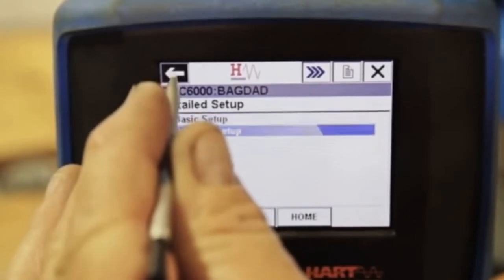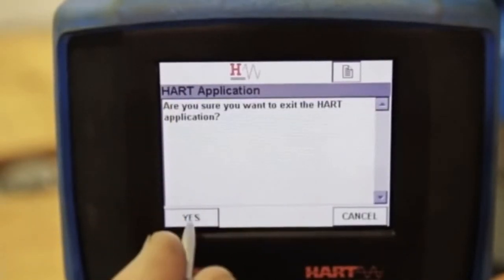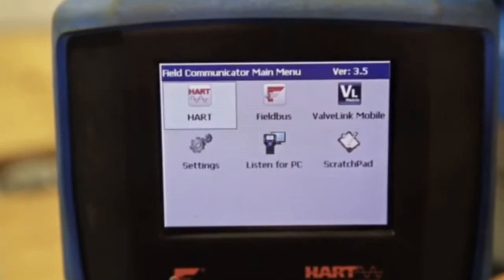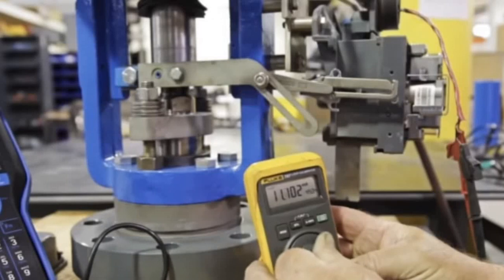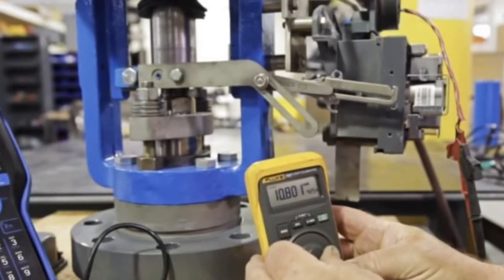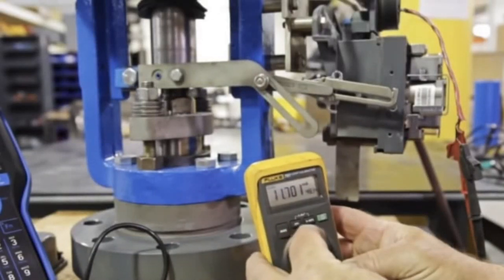Arrow back to exit out of all the screens. Select Yes to exit the HART application. Calibration is complete, and the valve should function normally with instrument signal.